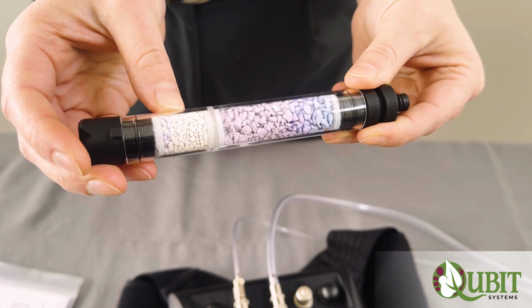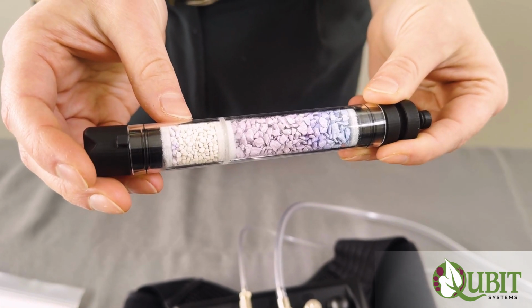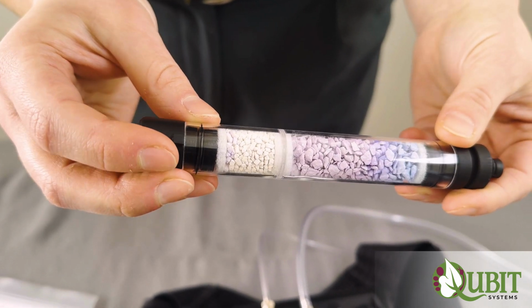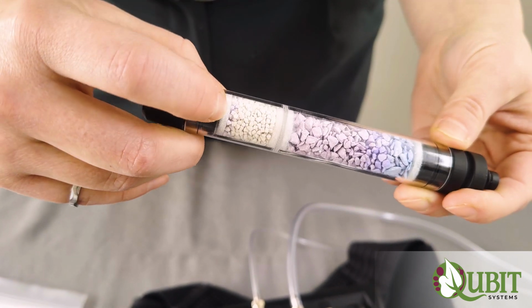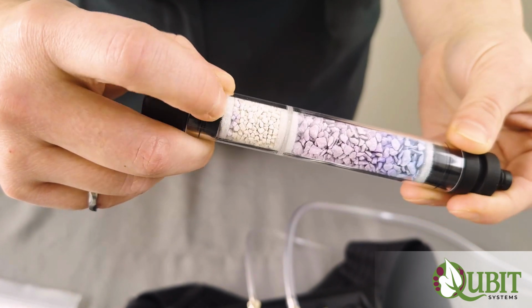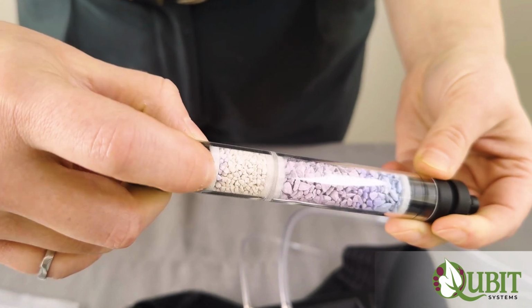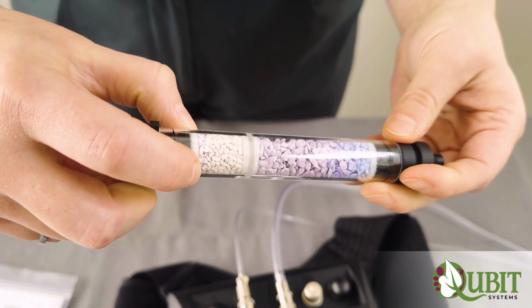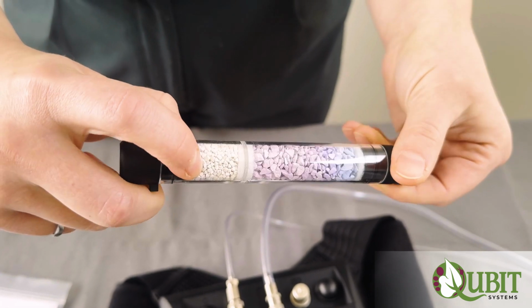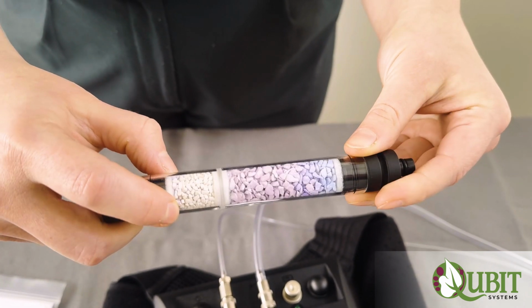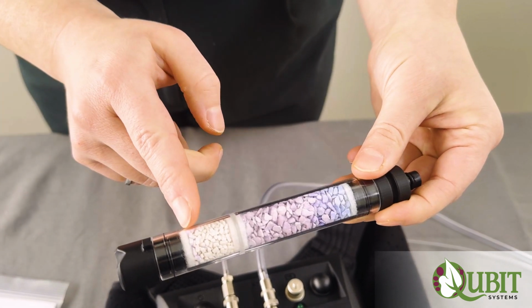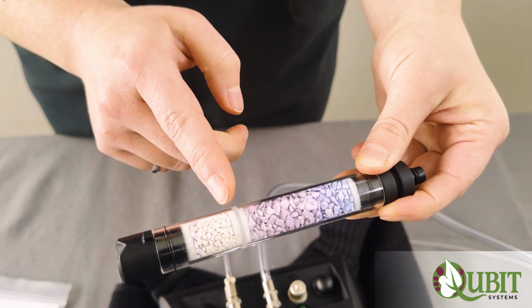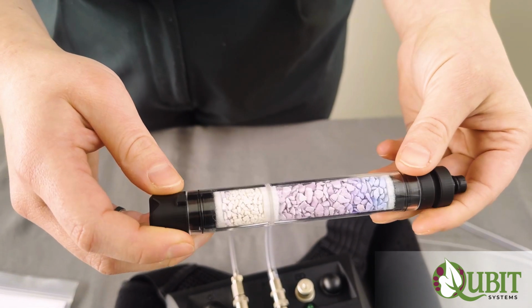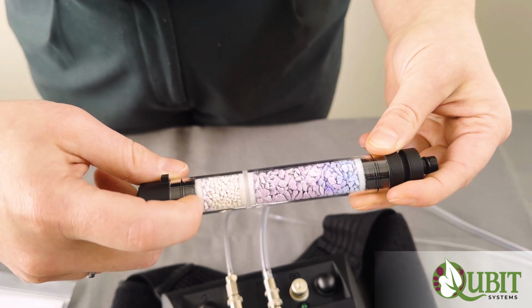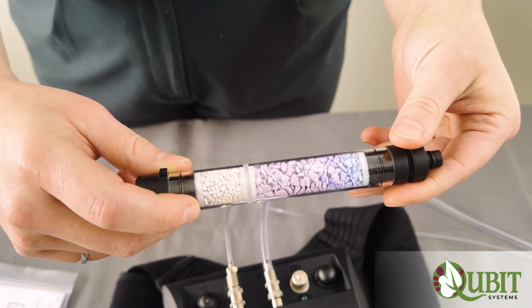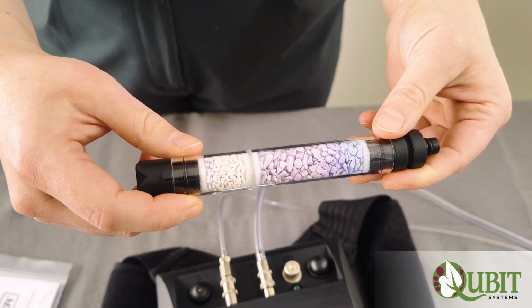As soda lime expires, it gradually turns purple as an indicator. It's important to note that this purple is very faint and pale, and here it might not even be visible on camera, but there is a little ring of purple near where the gas first comes in. This ring pattern is generally a good sign that the soda lime is expiring evenly, and gradually that purple will move across with use. However, if you notice a purple line at the bottom, it could be an indicator that the soda lime has fully expired and needs to be replaced.